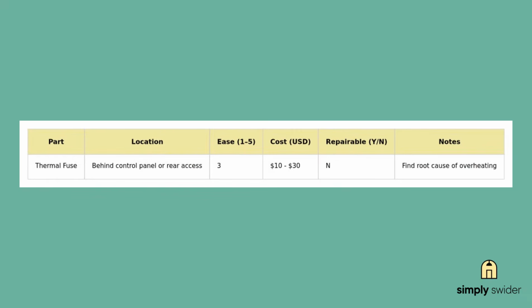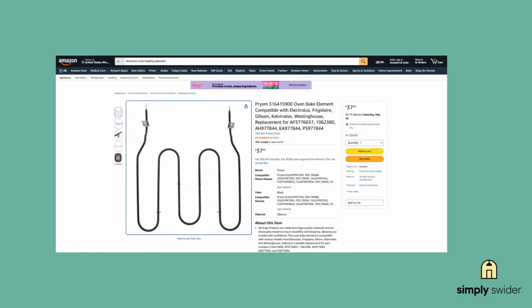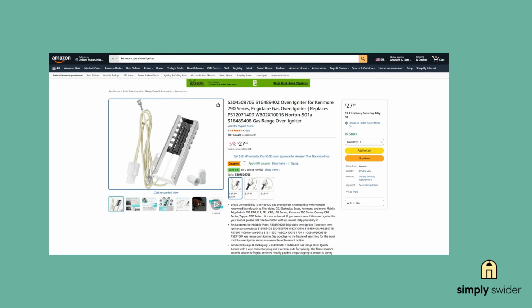circuit overloads. Let's talk real numbers here. The cheapest fix is usually a $10 thermal fuse if you're lucky. Most common waste of money, people spending $150 on a gas safety valve when a $35 igniter was the real problem. Biggest expensive mistake is replacing a control board for $300 to $700 when it was actually a $25 temperature sensor. Here's the money breakdown.